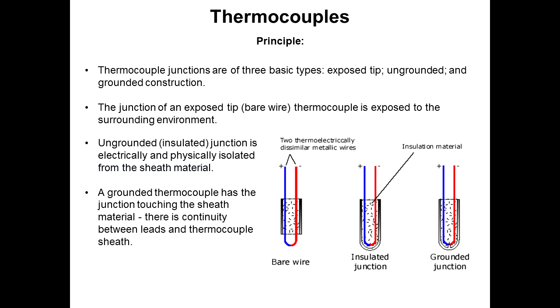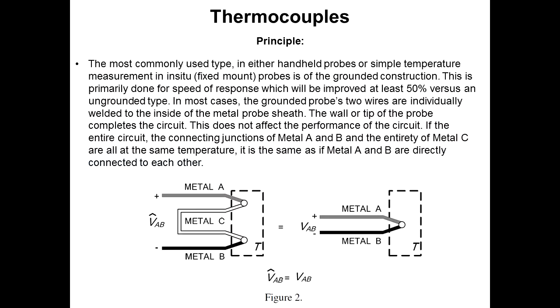Grounded thermocouples actually have the two wires welded to the inside of the metal sheath, and the metal sheath will complete the junction. So here we have a common type of grounded thermocouple, mostly used for handheld things and by people who want fast response but are not using control loops. The speed of response is generally at least 50% better than an ungrounded one. In these cases, the two wires are grounded individually to the inside of the metal sheath, and the tip of the probe completes the circuit. As long as that tip is the same temperature as both sides of this thermocouple junction, it's the same as them being connected together.